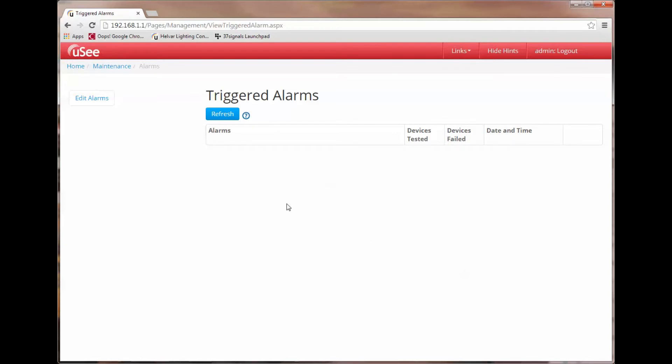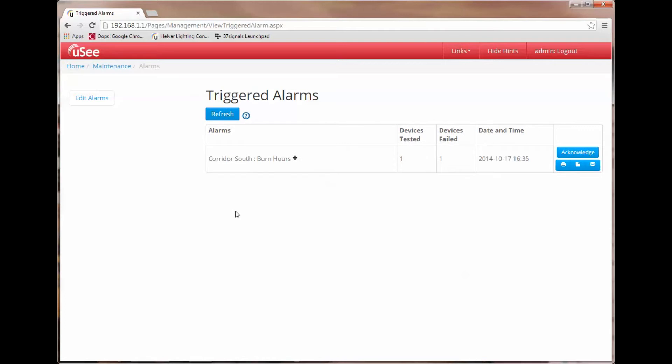If I now refresh the list again which will force the alarm to be tested against its threshold value, then the alarm will actually pop up again and it will be in the state where it is unacknowledged. Consequently the action associated with this alarm will be executed.